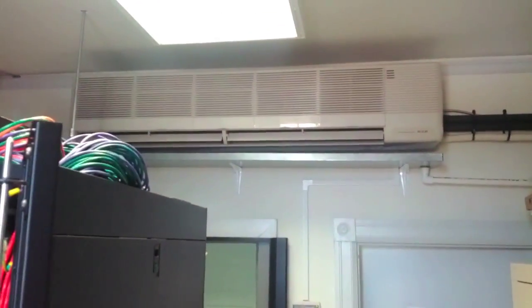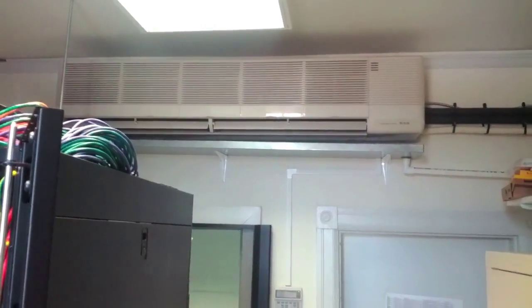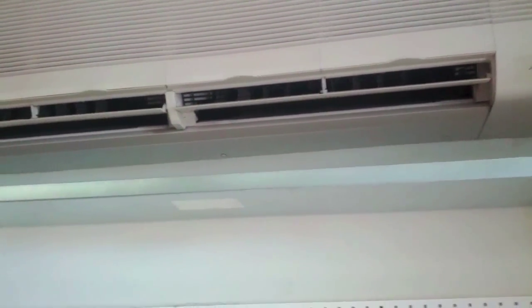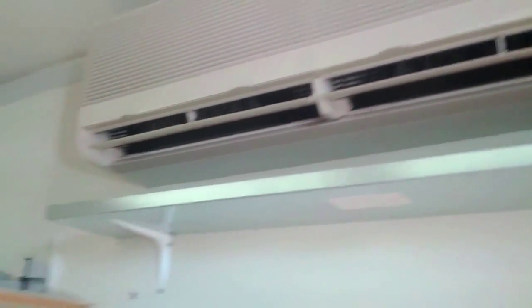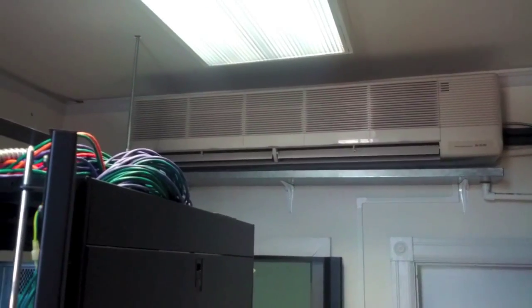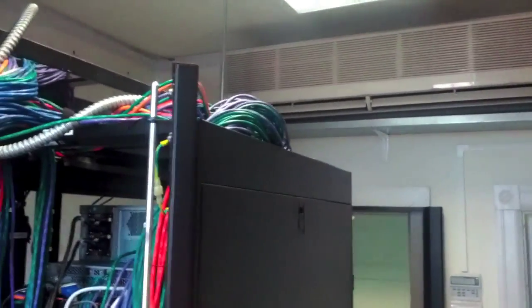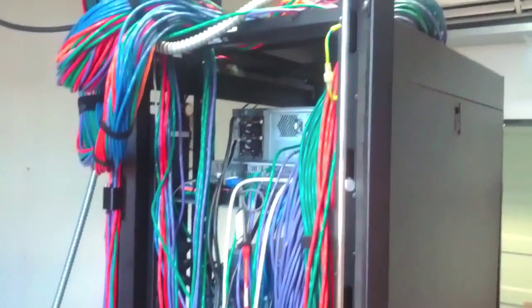And if you hear that whining sound, that's coming from our existing single functioning air conditioning unit up there. We'll look at the compressor outside in just a minute. We have a second unit that's currently not functioning at all. This one currently has a blockage in the coolant line, and this other one has a problem with the blower motor — the blower motor is about to burn out, but hopefully we can get another day or two out of it while we wait for parts for the other unit.